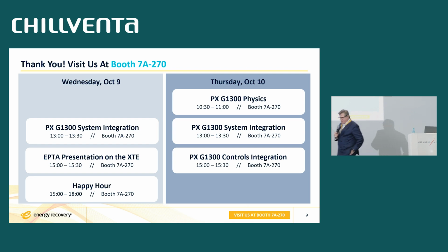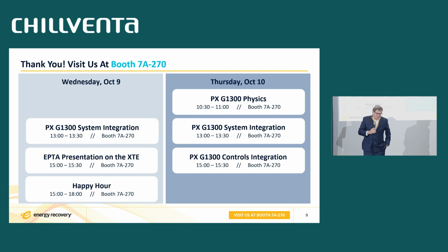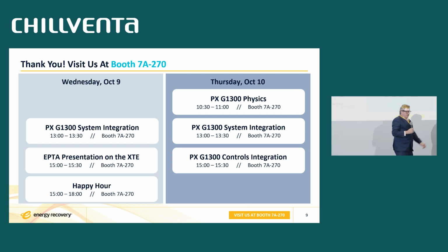Yes, sir. So, is it an alternative to an ejector? Yes. The question was, is it an alternative to an ejector? Well, it's a little bit of a different technology than an ejector. A high pressure ejector requires the implementation of a parallel compressor and an ejector. Basically, with this system, you can replace the parallel and the ejector. So it performs in a different way because it operates over a very wide range of the annual climate. Whereas the ejector operates in a fairly narrow band of high ambient, above 25 degrees ambient on the gas cooler. So it's a little bit different.